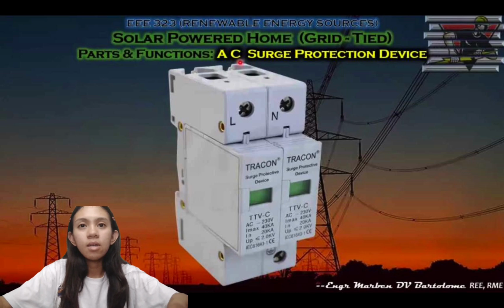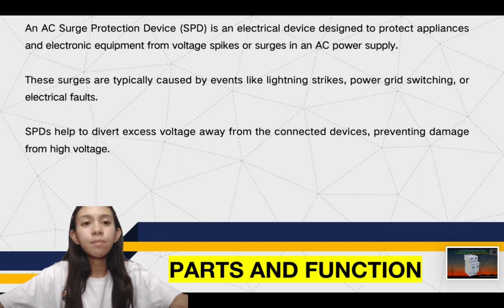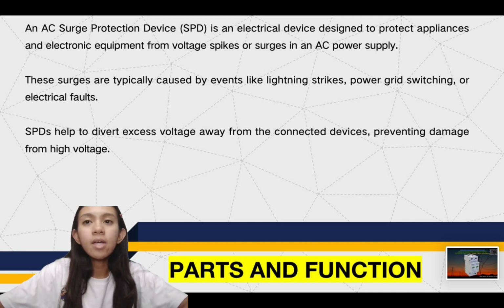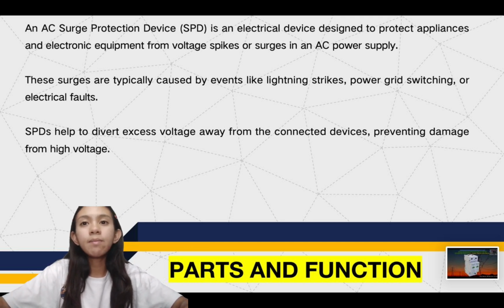Next is the AC surge protection device. An AC surge protection device is an electrical device designed to protect appliances and electronic equipment from voltage spikes or surge in an AC power supply. These surges are typically caused by events like lightning strikes, power grid switching, or electrical faults. SPD helps to divert excess voltage away from the connected devices, preventing damage from high voltage.